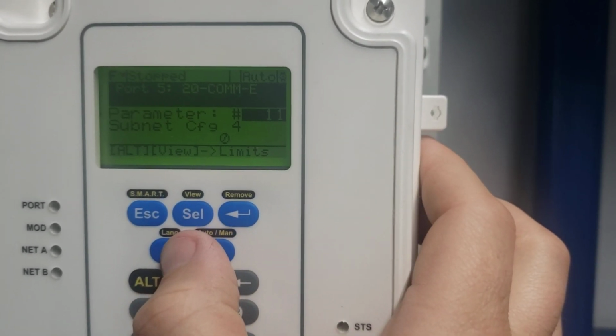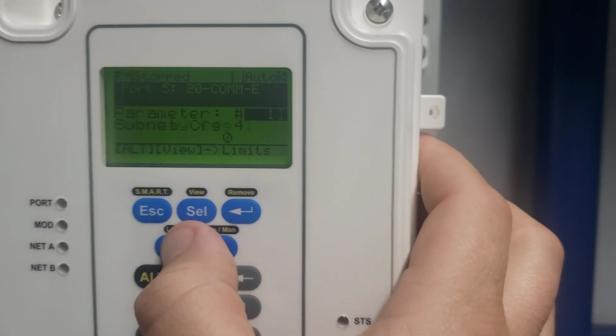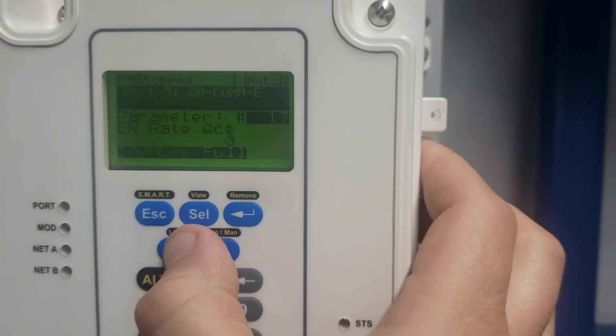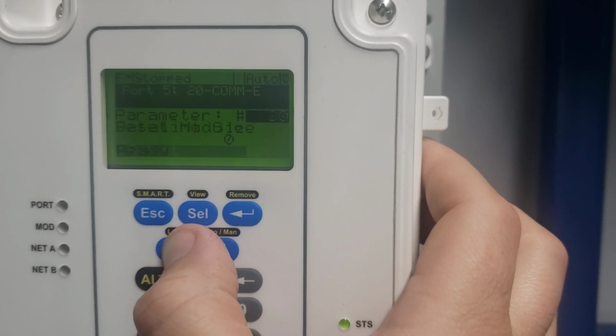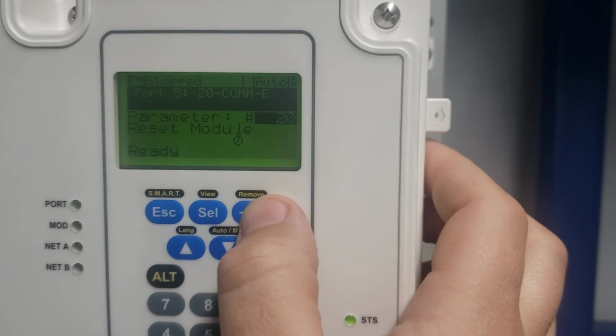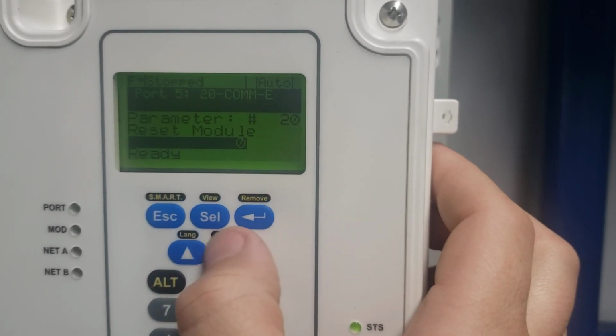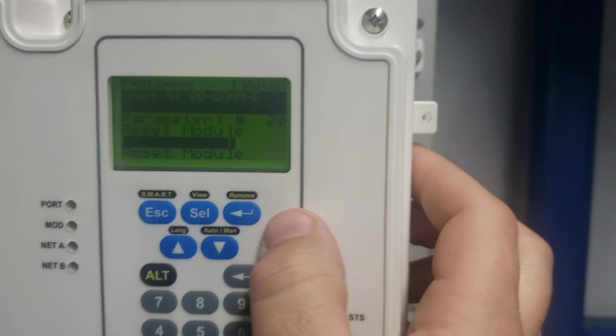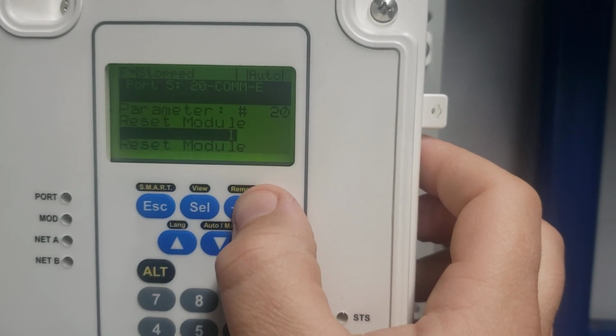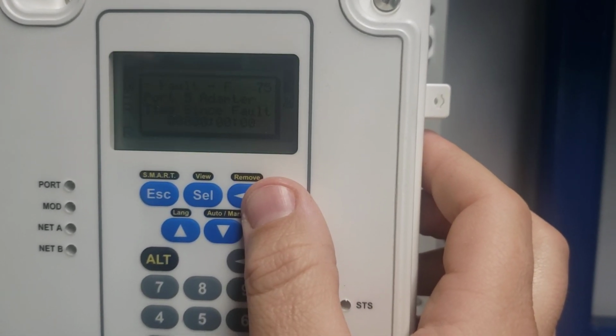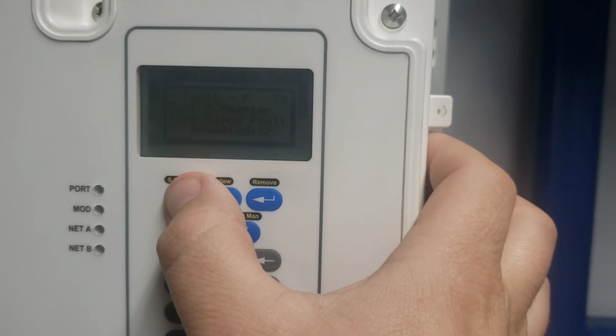After you've got the IP address and the subnet set, you're going to scroll up until you get to parameter 20, which is reset module. You hit enter to select it and change the value to a 1. This will power cycle the module when you hit enter. It'll likely cause a fault, but that's okay.